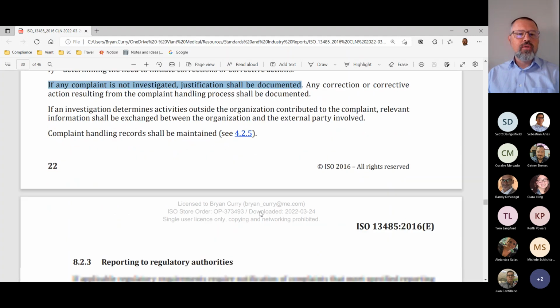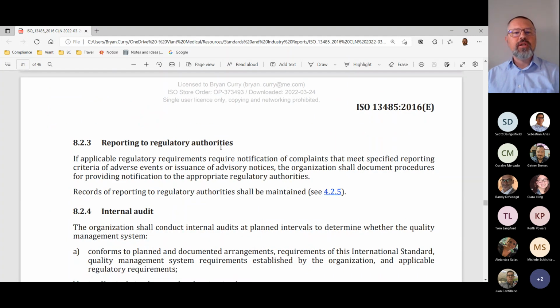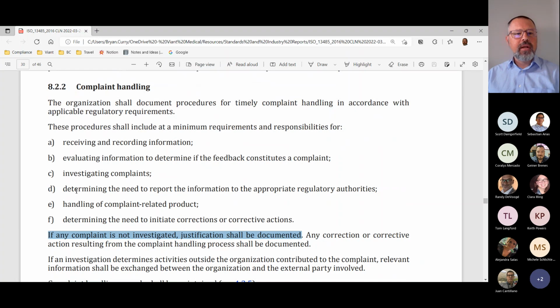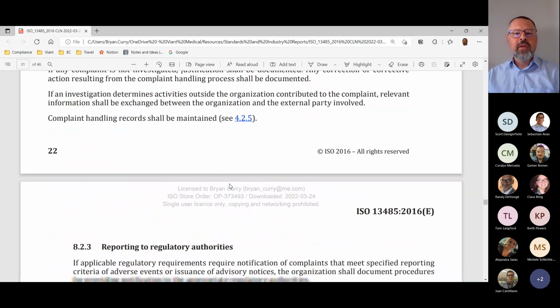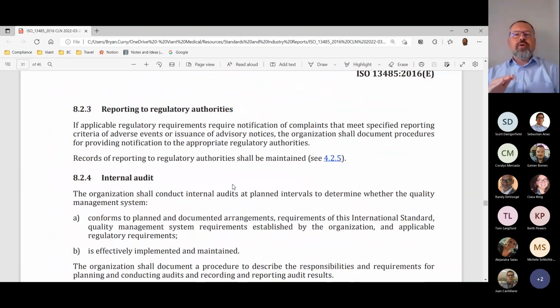I'm going to move forward to 8.2.3 and talk briefly about reporting to regulatory authorities, because you'll see that up here in 8.2.2 section D, where it talks about determining the need to report the information. So as a contract manufacturer, virtually all of our quality agreements pretty explicitly state that the responsibility for reporting to regulatory authorities lies solely with our OEM customers, largely because of a couple of factors. Number one, there's typically a clinical evaluation that needs to take place in order to determine if an adverse event occurred and whether or not you have to file, depending on the geography that you're filing the complaint in.